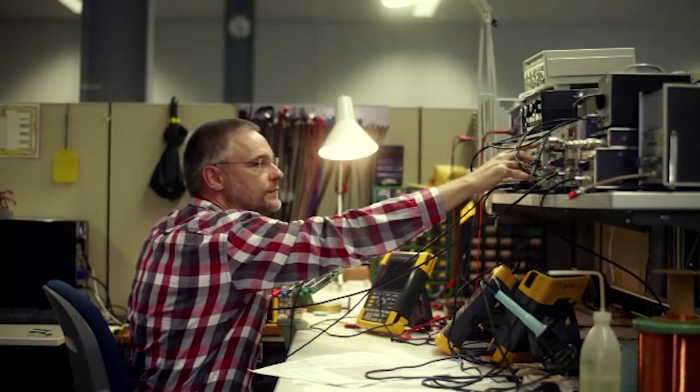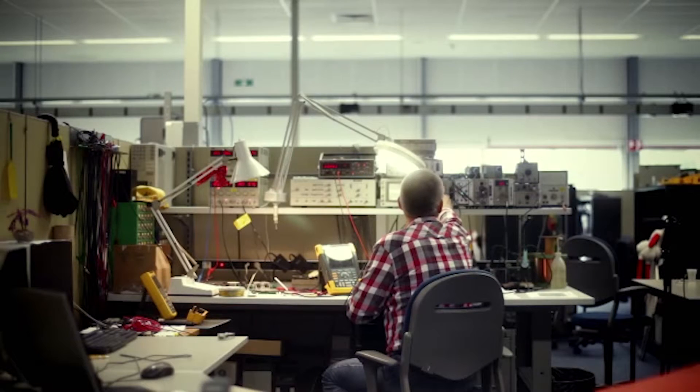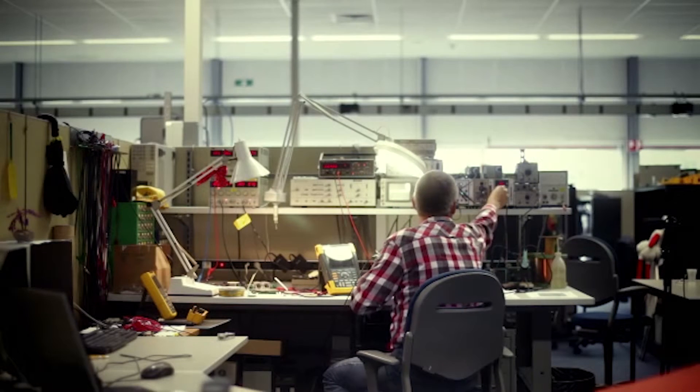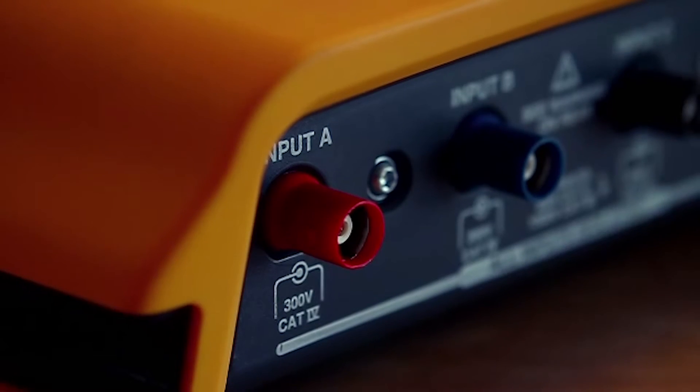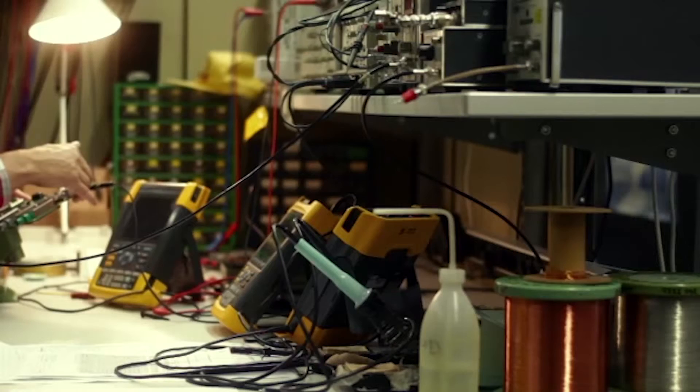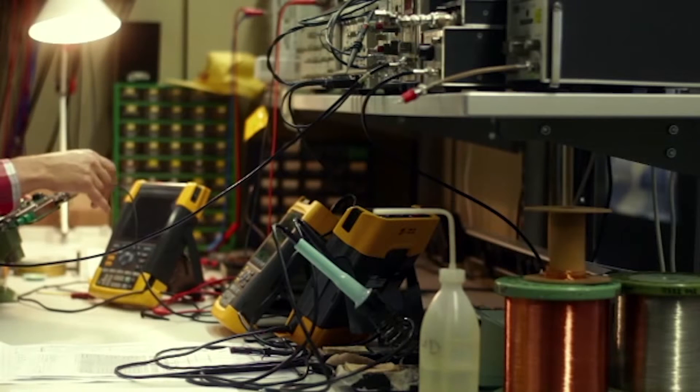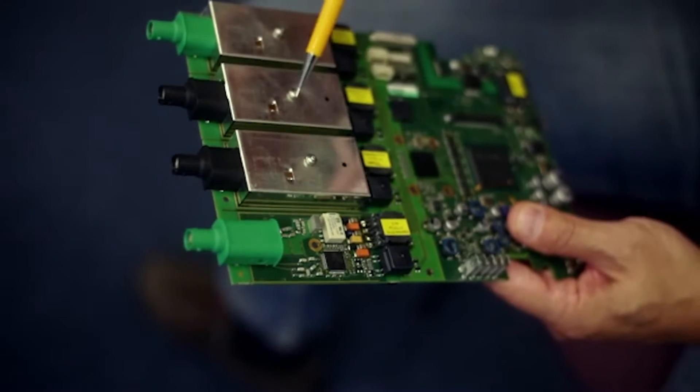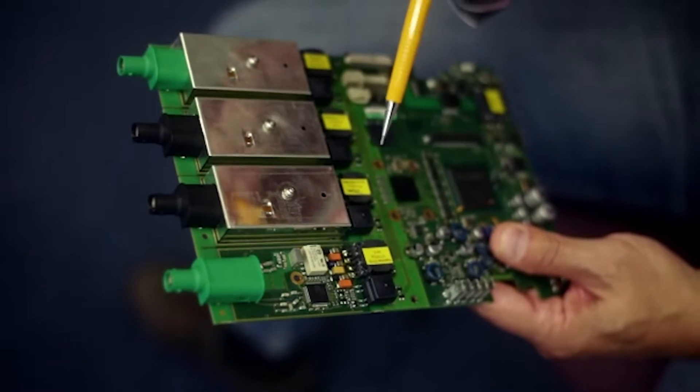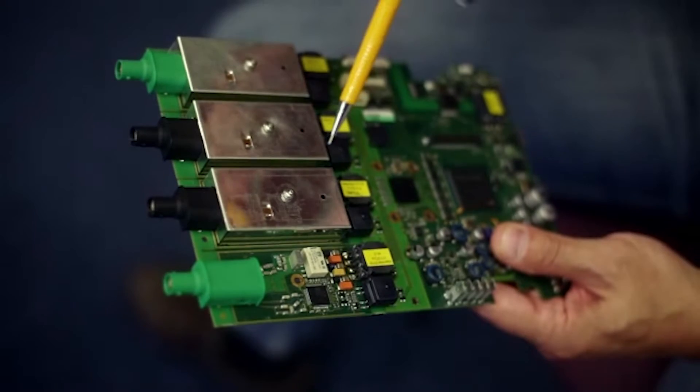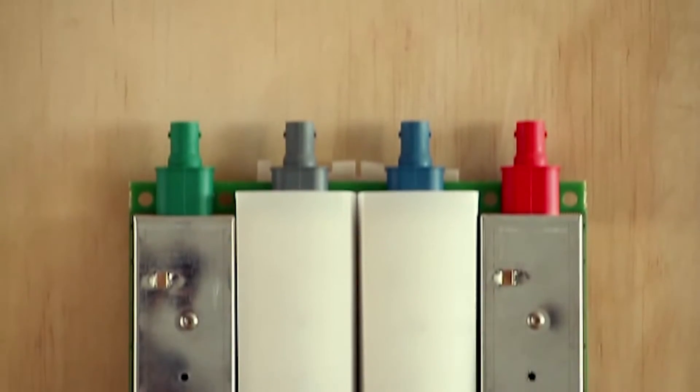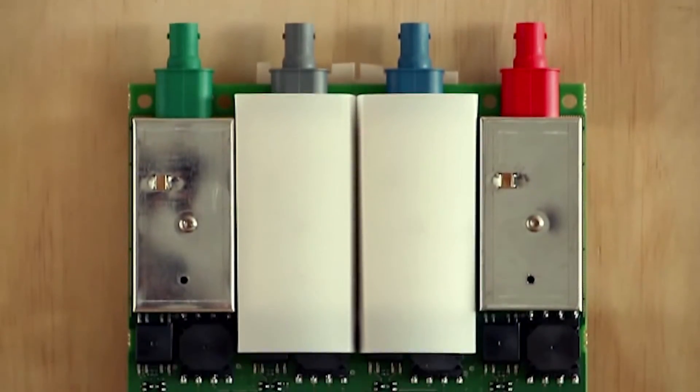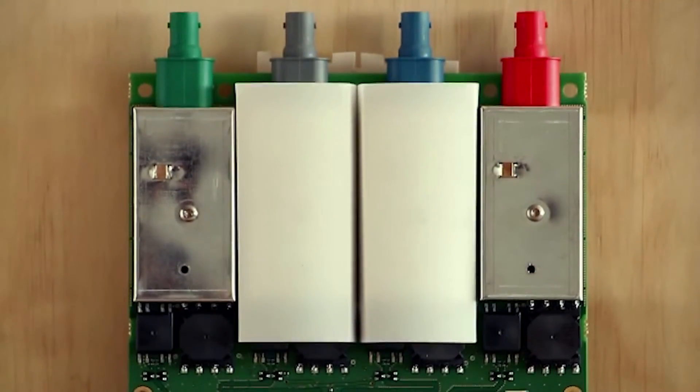The old instrument was suitable for category three and what we now did was make this instrument suitable for category four. That means you need larger clearances between conductors in your instrument, and also we had to make it narrower to comply with the four channel demand. So you have a problem.